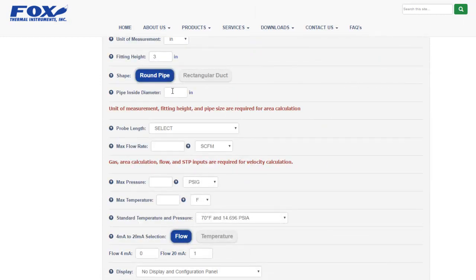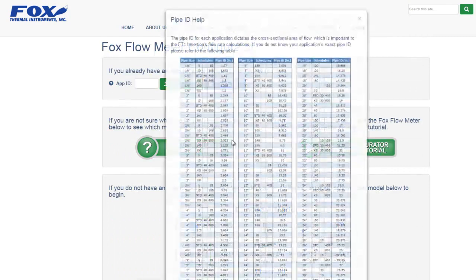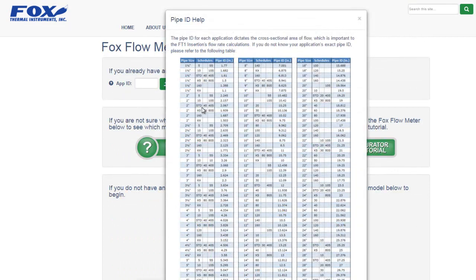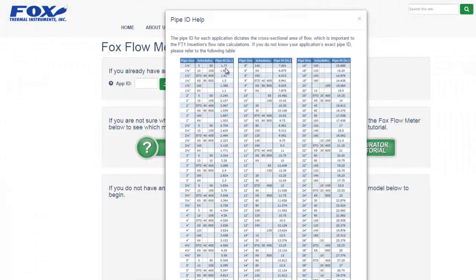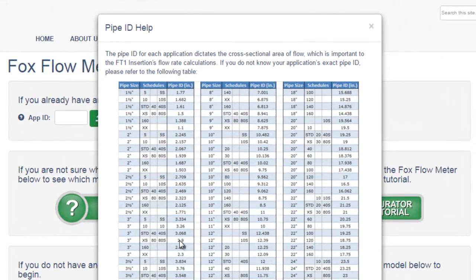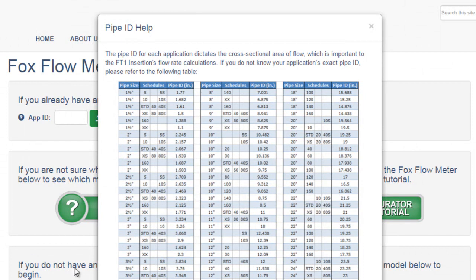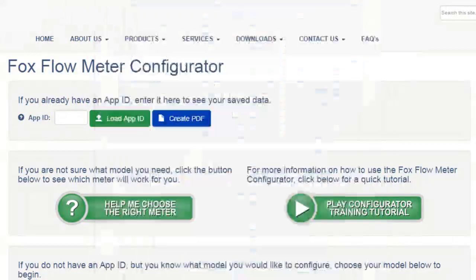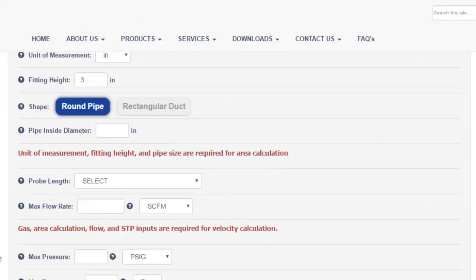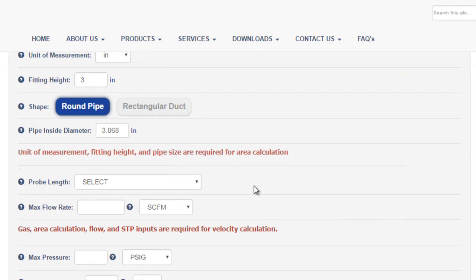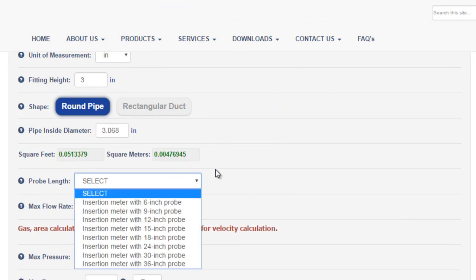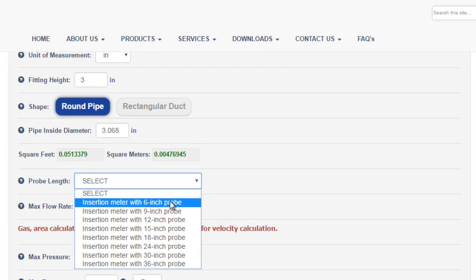Next is the pipe diameter. This is the pipe ID, not the general pipe size. If you know the schedule of your pipe, the help icon will give a table that shows a variety of pipe sizes and schedules with pipe IDs listed as well. For this configuration, let's assume a 3 inch schedule 40 pipe with an inside diameter of 3.068 inches. We'll enter that into the pipe ID field. Based on the fitting height and the pipe ID, a probe length will be recommended. You should generally choose the shortest probe length available.